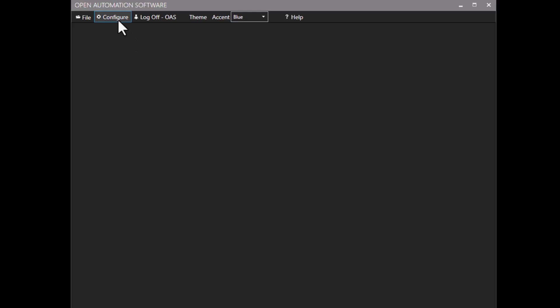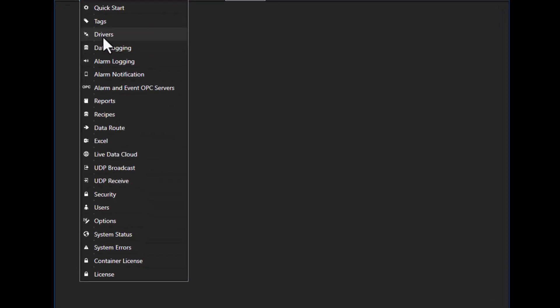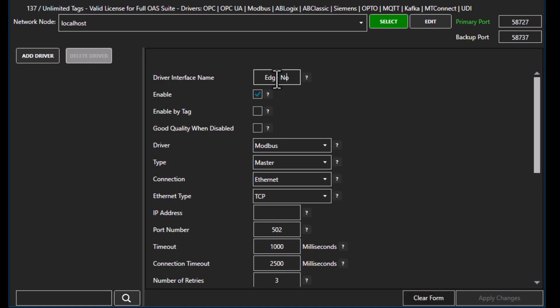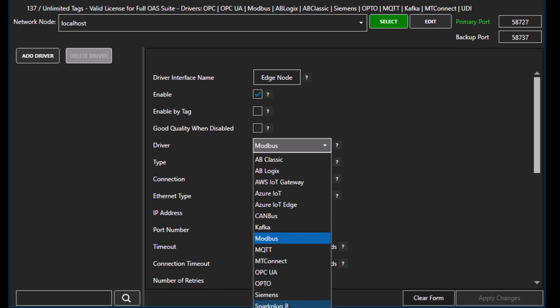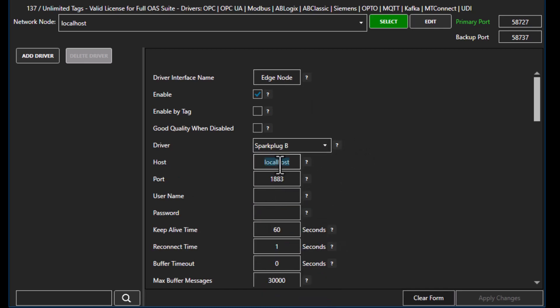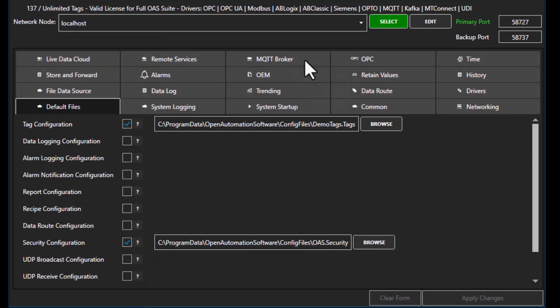In our first step we'll go to Configure Drivers. I'll give this driver a unique name — I'll just call it 'edge node' — and I'll set the driver type to Sparkplug B. I'll put in the host that I want to connect to. We can publish to any external broker or a local broker. OAS has a built-in MQTT broker running on the default port 1883 and can also be enabled for secure connections.